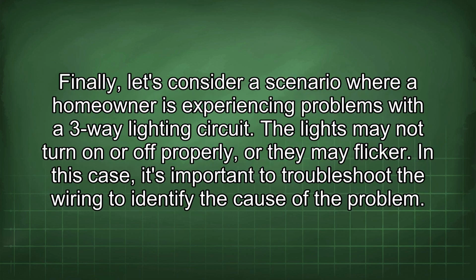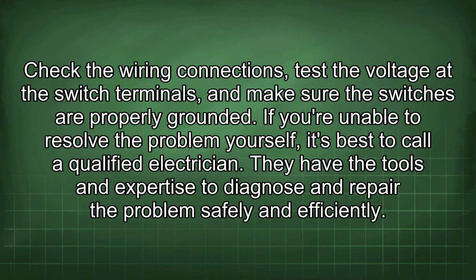Finally, let's consider a scenario where a homeowner is experiencing problems with a 3-way lighting circuit. The lights may not turn on or off properly, or they may flicker. In this case, it's important to troubleshoot the wiring to identify the cause of the problem. Check the wiring connections, test the voltage at the switch terminals, and make sure the switches are properly grounded. If you're unable to resolve the problem yourself, it's best to call a qualified electrician. They have the tools and expertise to diagnose and repair the problem safely and efficiently.